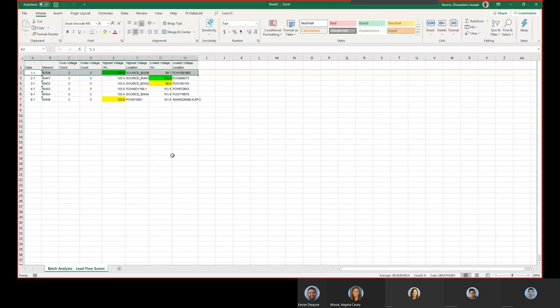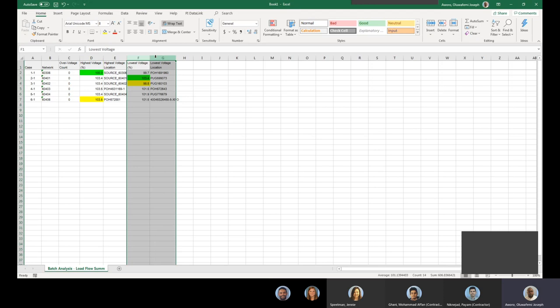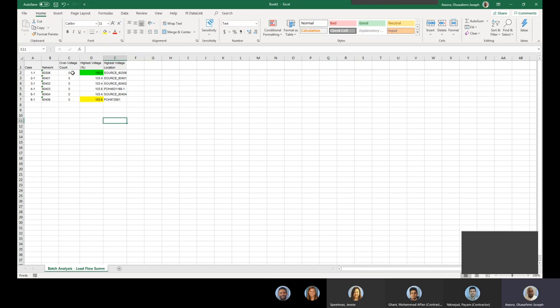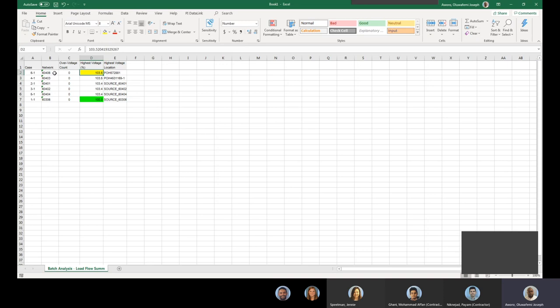So I'm going to share the Excel report. This Excel report, we are interested in the high voltage so we can delete the under voltage count. So over voltage count is zeros. What this means is there's no node on the feeder where there was an over voltage on that particular day at that time, so which means that's great. And the highest voltage, if you sort these, I will always want to sort from the smallest. So the highest voltage we have is 103.5 on this feeder.